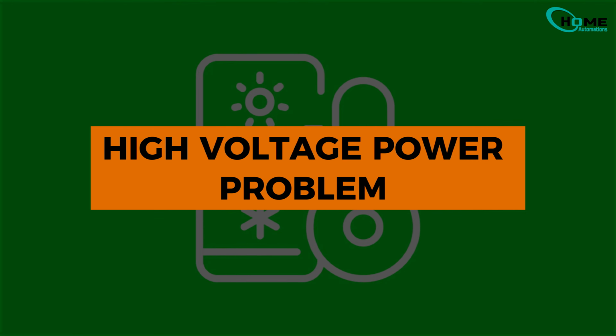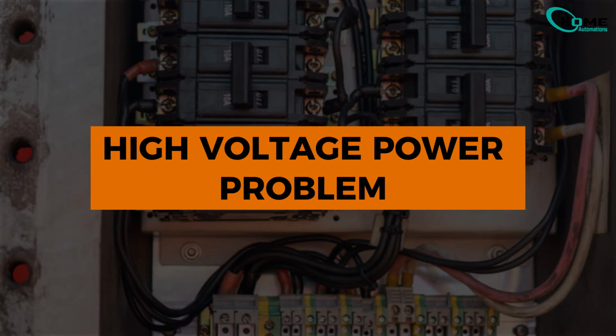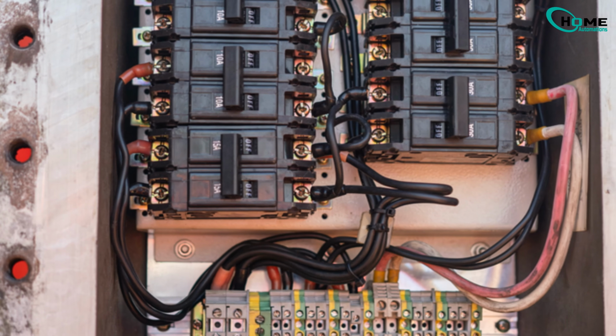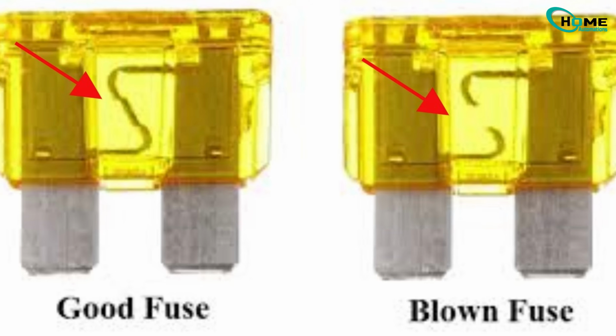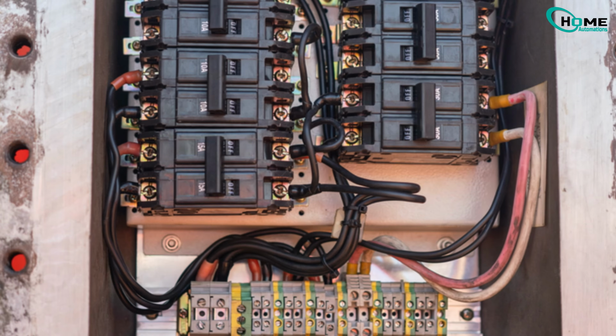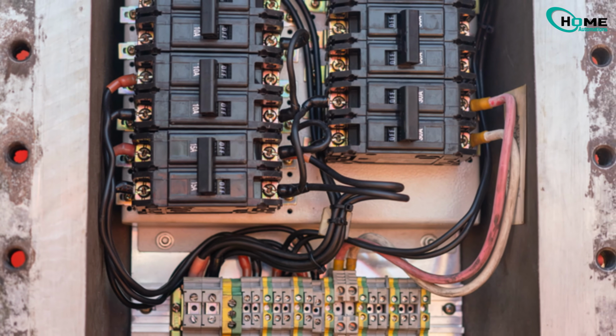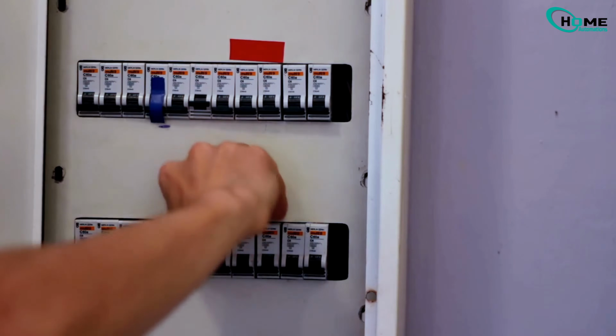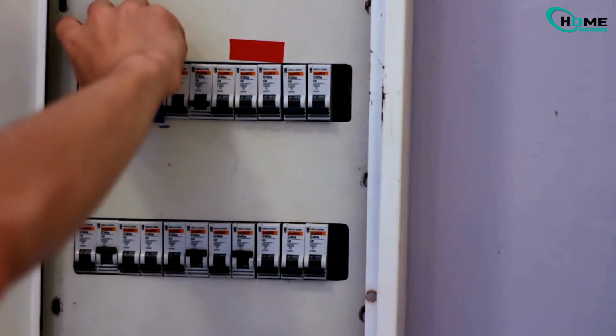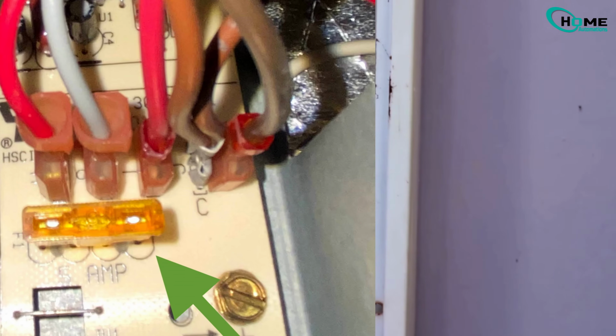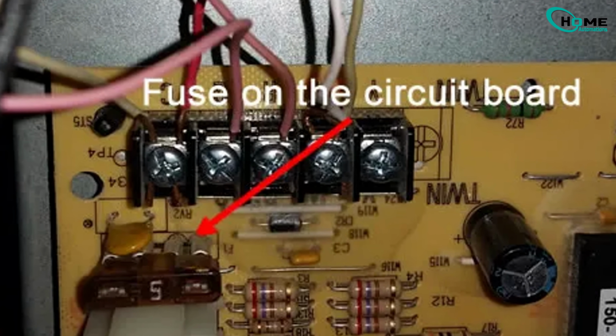2. High voltage power issue. Your system could have lost power due to a tripped breaker, a blown fuse, or a bad disconnect. Sometimes this happens after a power outage. If you're comfortable, you can try resetting the breaker once. But if it trips again, stop there. That means there's an underlying problem that needs a pro.